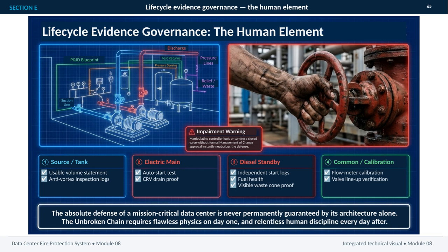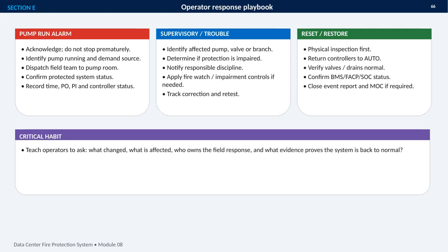For the source or tank, that means confirming usable volume and reviewing anti-vortex inspection records. The electric main requires proof of automatic starting and CRV drainage. The diesel standby adds independent start logs, fuel condition, and visible waste cone evidence. Finally, common systems depend on calibrated flow meters and verified valve lineups. The critical point is that unauthorized changes can defeat the defense immediately. Manipulating controller logic or turning a closed valve without formal management of change approval removes confidence in the protection. The unbroken chain, therefore, depends on sound physics at commissioning, followed by disciplined human verification every day.